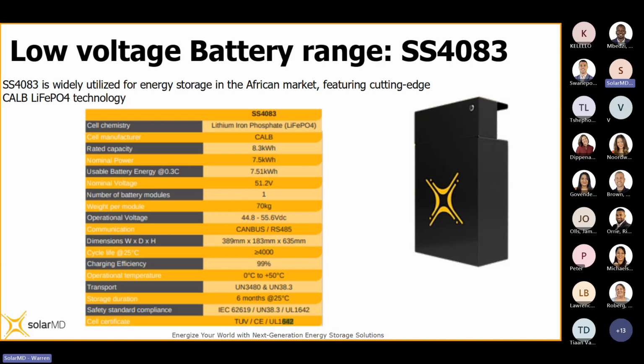There are some situations where you don't have control over this. I say this, it's not a brand-specific challenge, it applies to anyone using this battery chemistry. You want to make sure the environment is at room temperature, around 25 degrees or a bit less, very much like the temperatures the average human would enjoy. That's the temperature these batteries would want to operate at for extended periods. You don't want to install this battery where it's 30, 40, 50 degrees. You can, but you will greatly degrade the lifespan of the product.